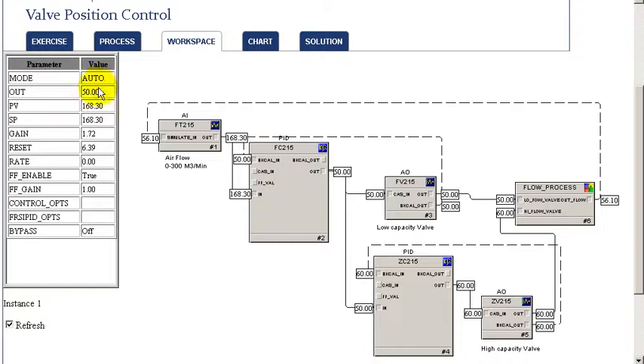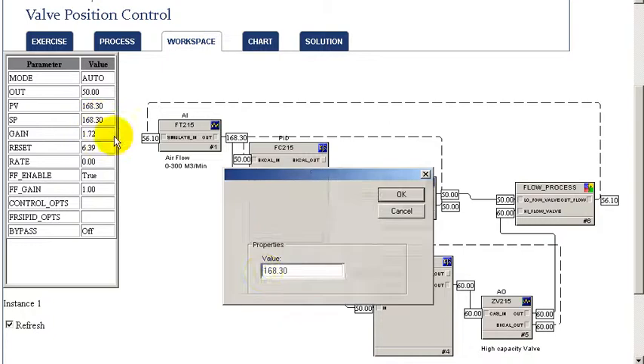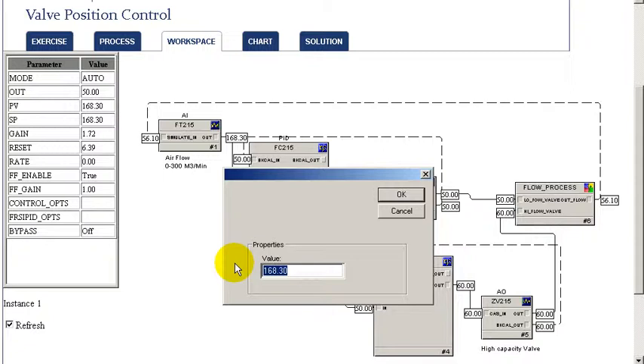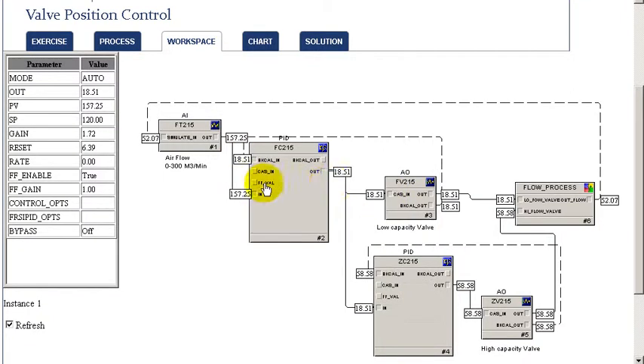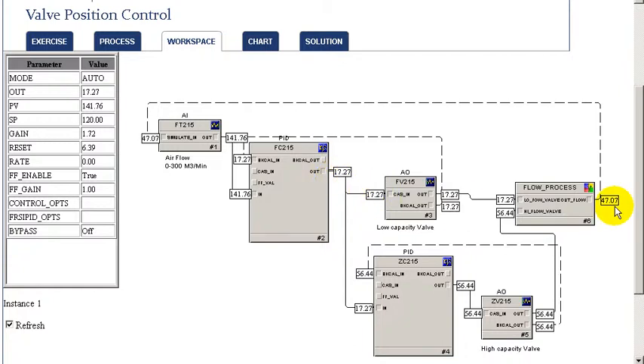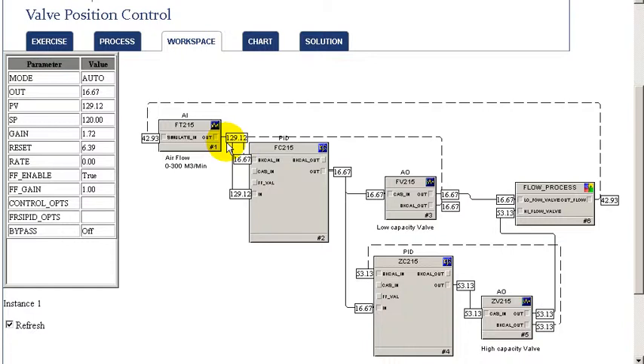To start our exercise, we'll look and see the PID is already in auto, so we can go ahead and change the initial target to 40% of range, which in this case turns out to be 120. And so as we can see very quickly, the smaller valve takes action to achieve our new target flow.